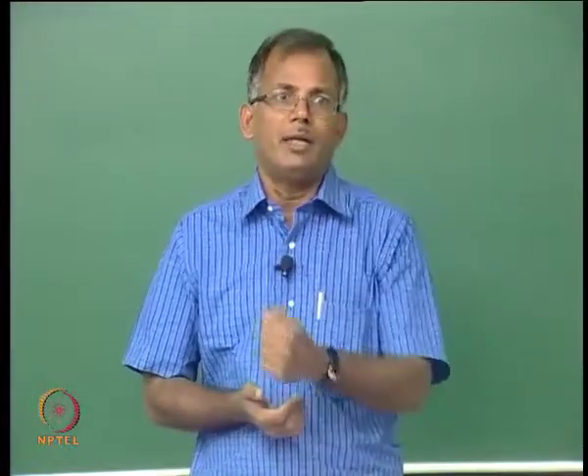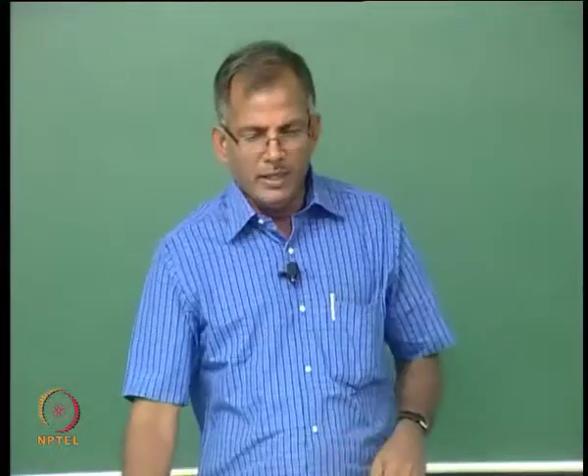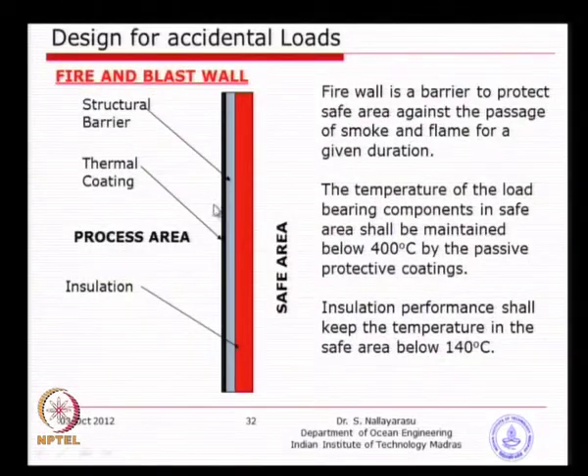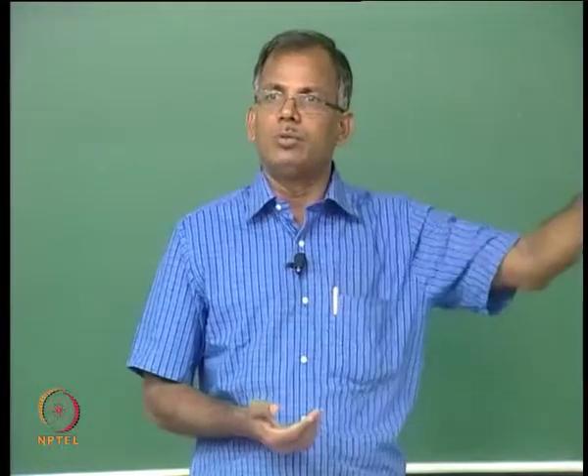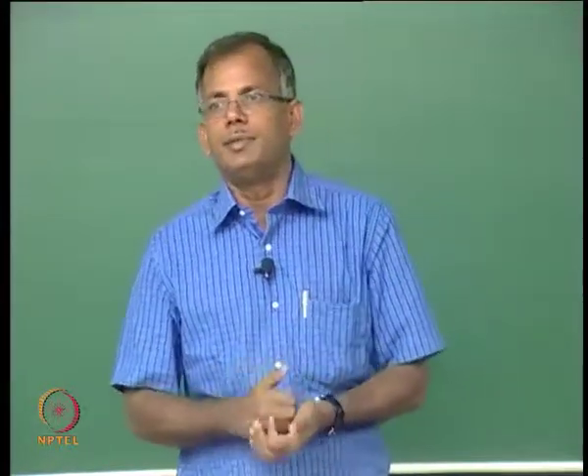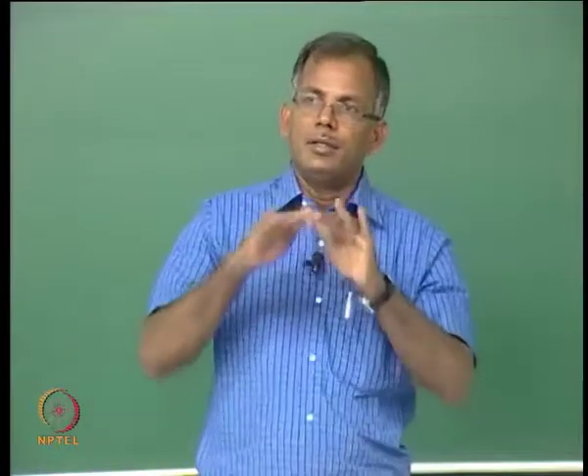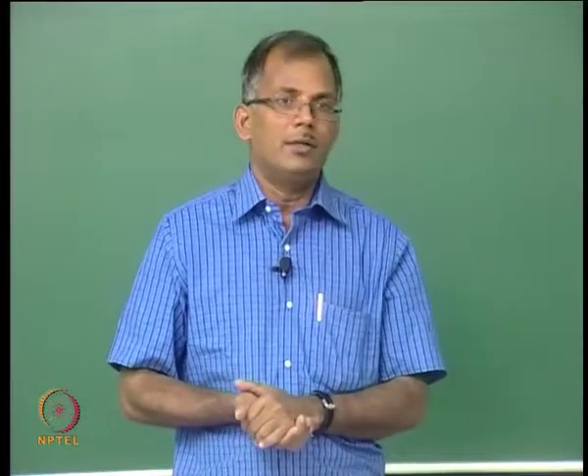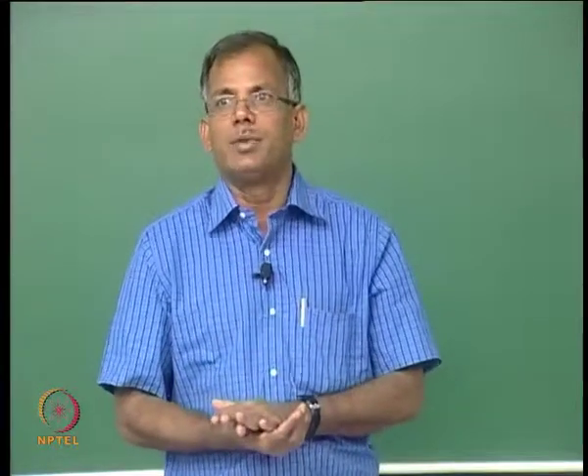The structural barrier performs blast resistance duty — when loading is applied from either side, the structure deforms. When there is fire, the first requirement is to safeguard the structural material from increased temperature. The thermal coating reduces the temperature: if it is 1,000 degrees externally, the structure will only see a reduced value of perhaps 100–200 degrees, because up to about 400 degrees the material deformation remains limited and the stress-strain characteristics remain under control.